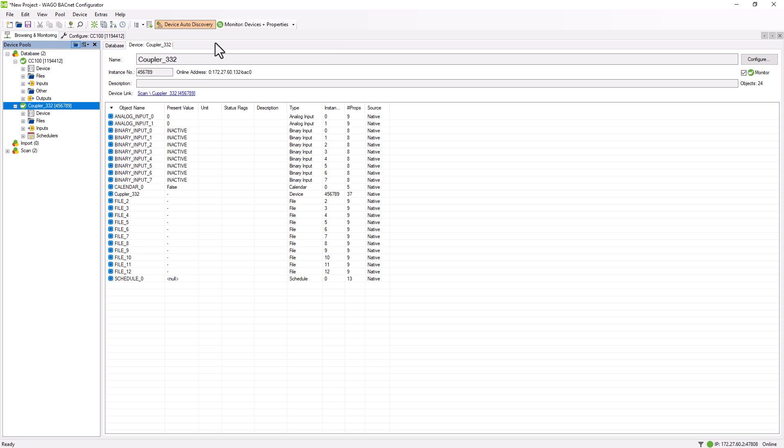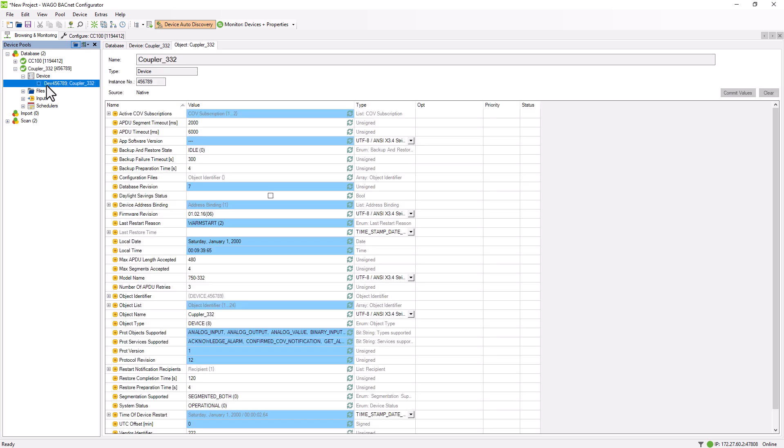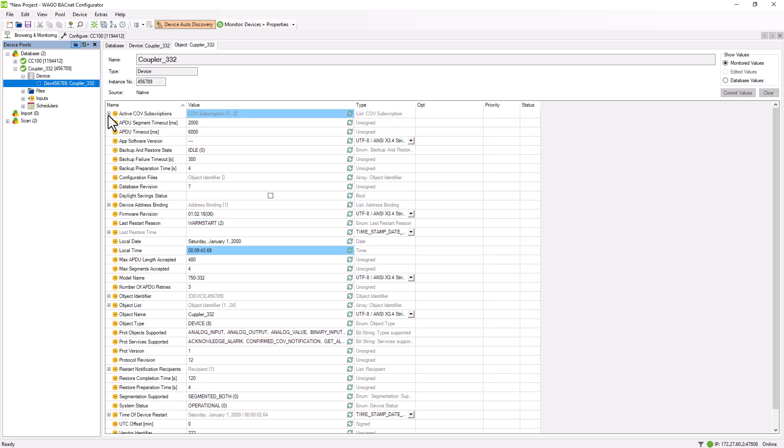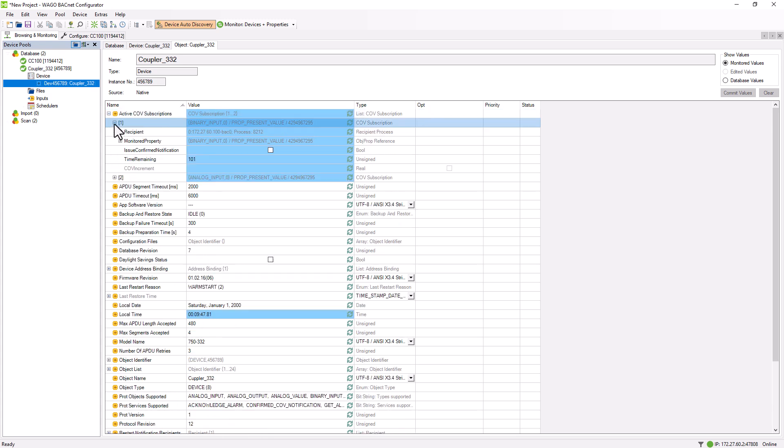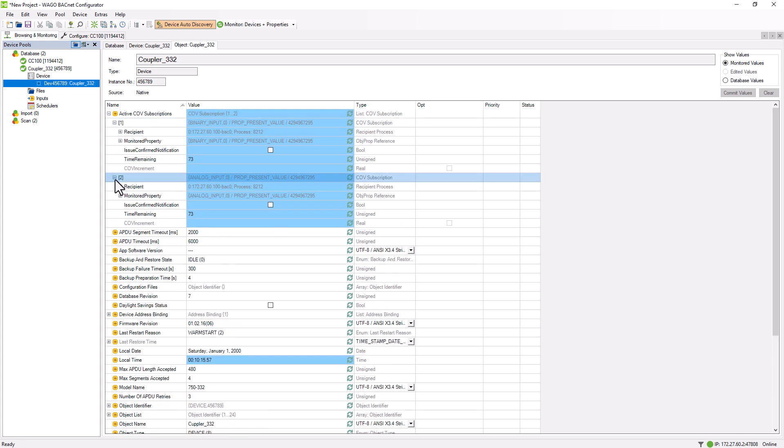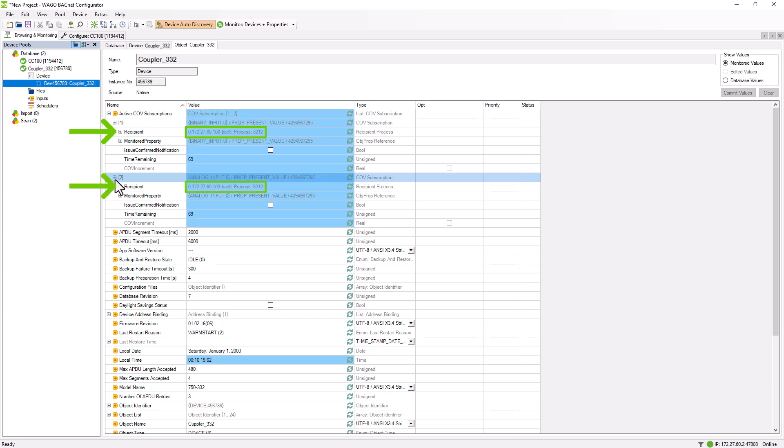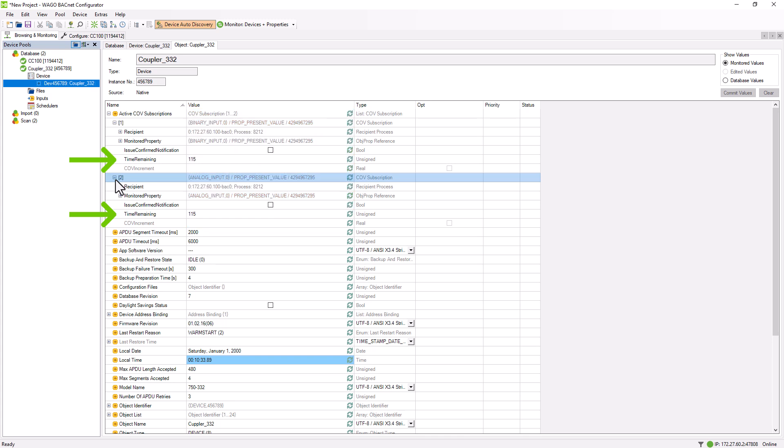All COV subscribers on a server are shown in the property Active COV Subscriptions, found in the device object at the top. With the plus sign, the subscribed values are displayed, including the subscriber's IP address. Here, we also see the time remaining, indicating how long the subscription is valid. After 60 seconds, the countdown resets to 120 seconds, as a new subscribed COV telegram is received and the countdown restarts.